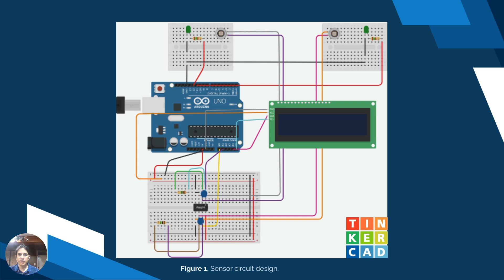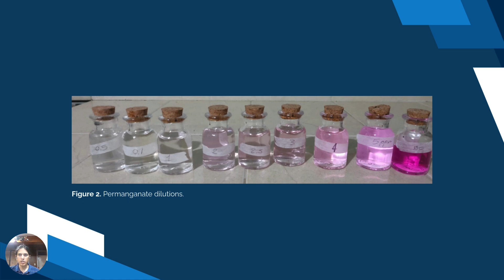Passing to the results, here is the sensor circuit design, which is simple and reproducible with off-the-shelf parts. Here we had different MnO4 dilutions ranging from 0.1 to 50 ppm. Here is the device functioning. We can see on the left the interior of the device, and on the right we can see the LCD displaying the results of the samples. Finally, the sensor achieves manganese detection from 0.1 ppm with 0.5 ppm resolution, providing compliance monitoring capability against Mexico's 0.15 ppm water quality standard.